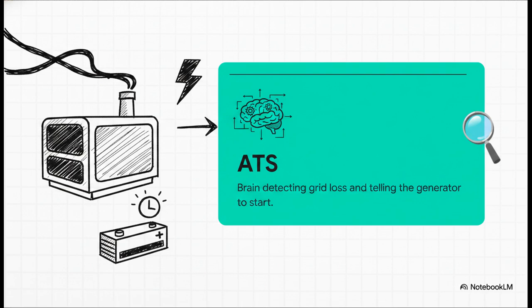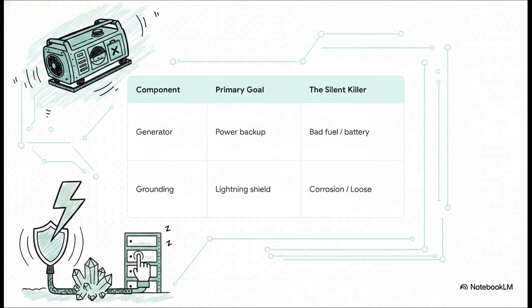But here's the catch. That generator relies entirely on the ATS, or automatic transfer switch. If a site loses power but the generator doesn't kick in, the fault is almost always in this clever little piece of logic, not the physical engine itself. It's essentially the brain that detects the exact microsecond the grid drops and issues the command to start firing. When you look at these primary survival systems, it's wild how the simplest things can cause absolute chaos.